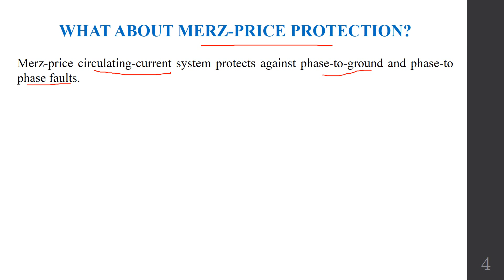But in case of inter-turn fault, the current produced by inter-turn fault flows in a local circuit and is not able to create a difference between the entering current and the leaving current. Therefore, in that case, the relay will not be getting any amount of current and will be acting like a normal condition. Therefore, the Merz price protection scheme cannot be applied for stator inter-turn fault protection. And thus, we need a separate protection scheme for inter-turn faults occurring in stator of generator.